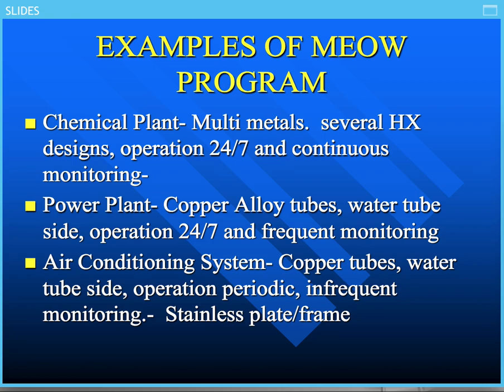But in this case, it would say, okay, I have to have a good corrosion inhibitor because I have multi-metals. Is that for mild steel or copper alloys? Then I have to have a good dispersant to maintain less fouling, not only in the cooling tower but also in the heat exchangers, and that continuous monitoring will provide you that input as to how effective that program is.